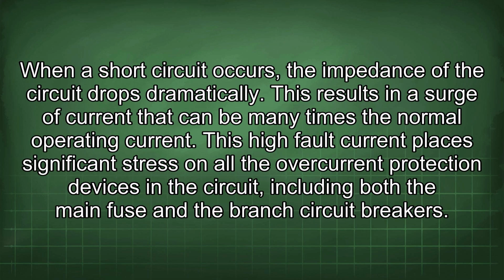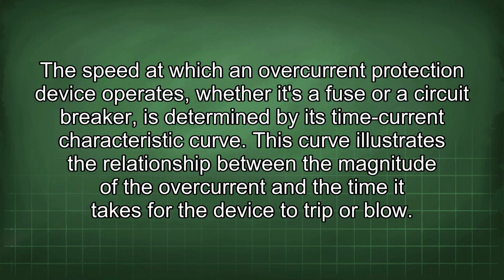When a short circuit occurs, the impedance of the circuit drops dramatically. This results in a surge of current that can be many times the normal operating current. This high fault current places significant stress on all the overcurrent protection devices in the circuit, including both the main fuse and the branch circuit breakers. The speed at which an overcurrent protection device operates, whether it's a fuse or a circuit breaker, is determined by its time current characteristic curve.